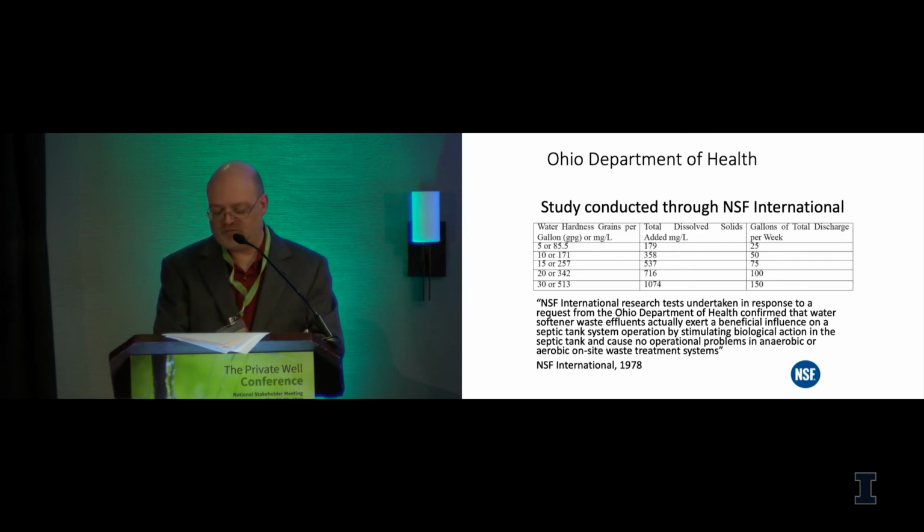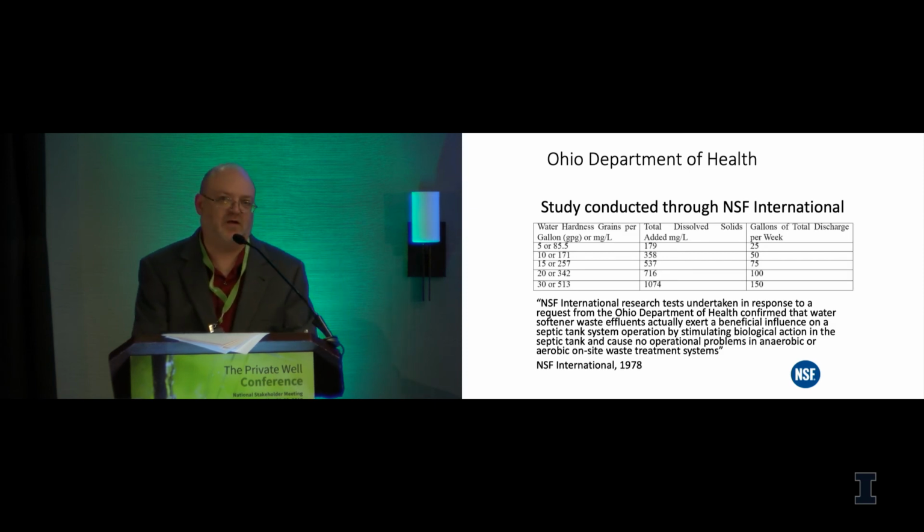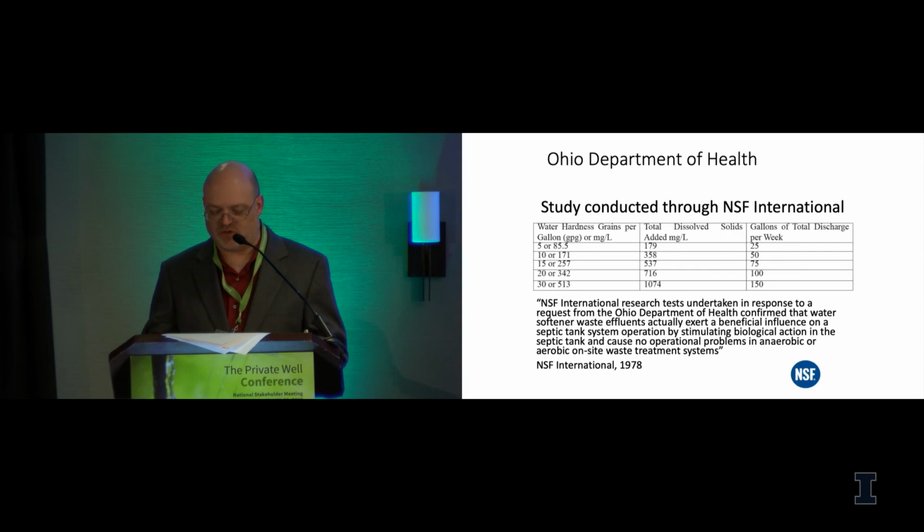And their conclusion from this study: NSF International research tests undertaken in response to a request from the Ohio Department of Health confirmed that water softener waste effluents actually exert a beneficial influence on the septic tank system operation by stimulating biological action in the septic tank and cause no operational problems in anaerobic or aerobic on-site wastewater treatment systems. So we'll touch on that again. I'll come back to that topic, but they actually noticed a slight beneficial impact of the discharge.